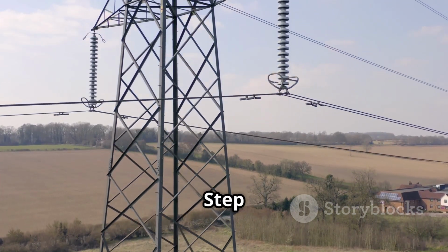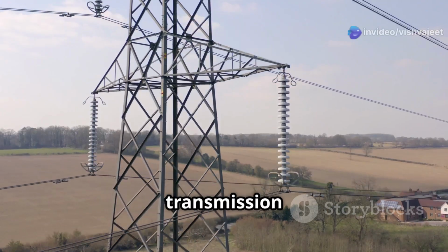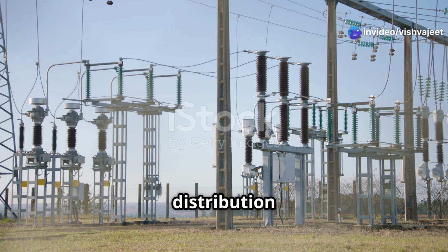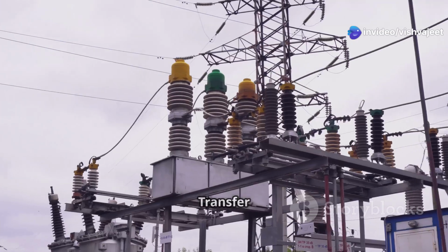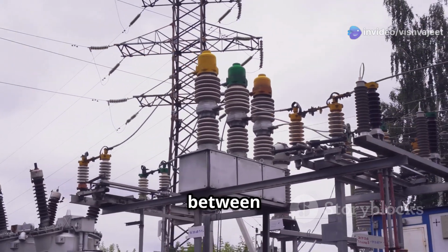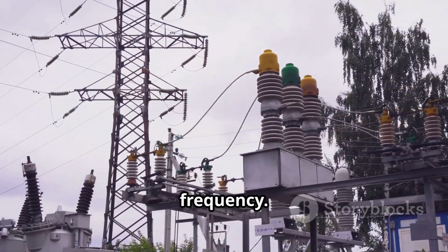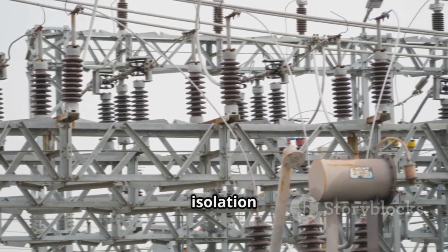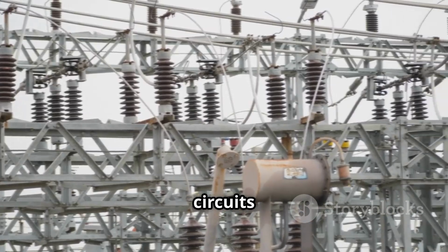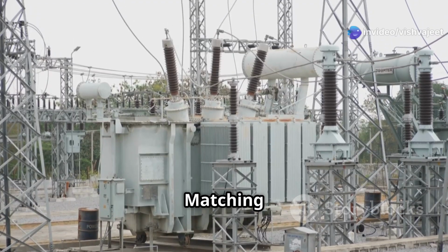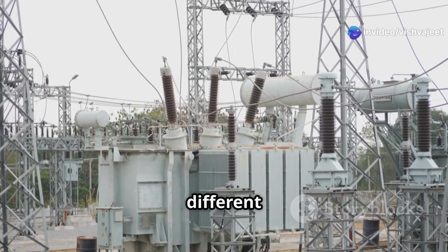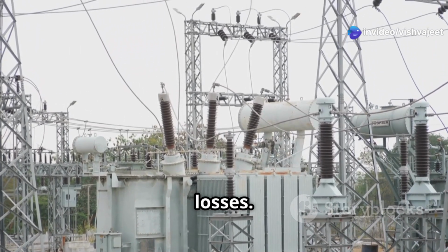Voltage transformation: step-up voltage for efficient long-distance transmission or step-down voltage for distribution to end users. Power transfer: transfer electrical energy between circuits without changing frequency. Isolation: provide electrical isolation between primary and secondary circuits for safety. Impedance matching: match impedance between different sections of the power system to minimize losses.